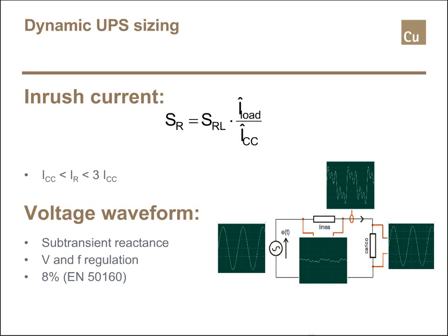Typically, a dynamic UPS is able to provide 300% of its rated current, and this is more or less the limit to be considered.